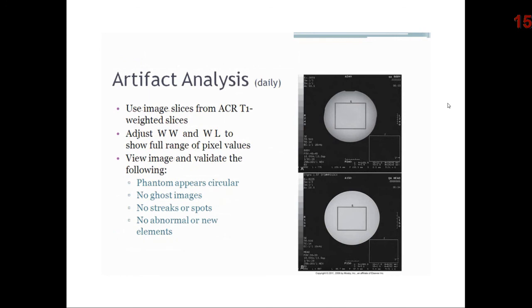The MRI technologist should be evaluating daily phantom images for any signs of artifacts. Artifacts can differ according to image conditions, such as pulse sequence parameters, choice of RF coils, and with individual patients. Artifacts can be an early sign of equipment failure.